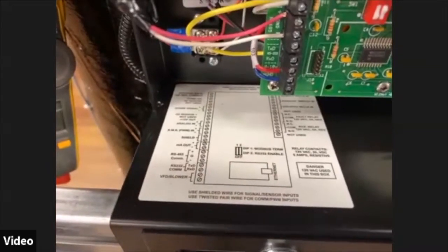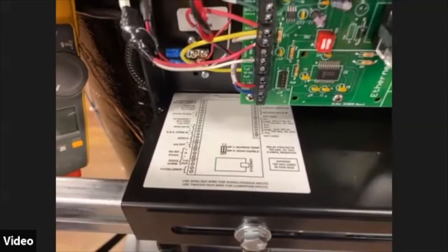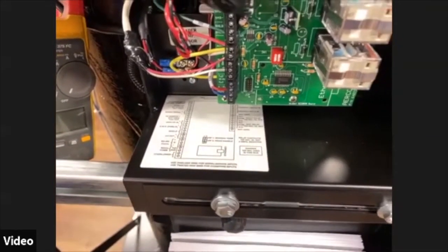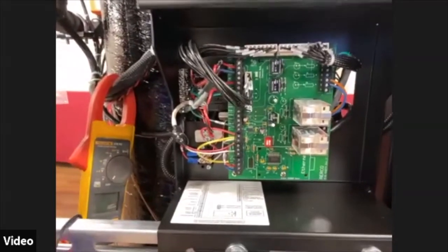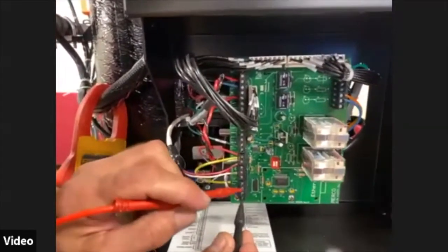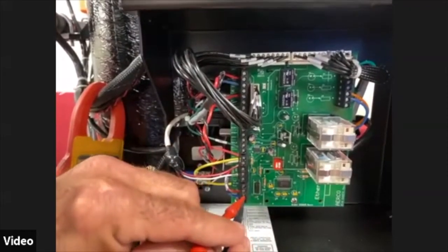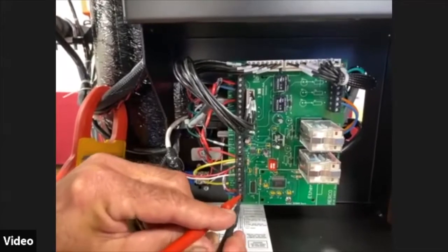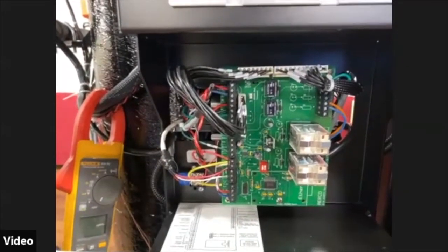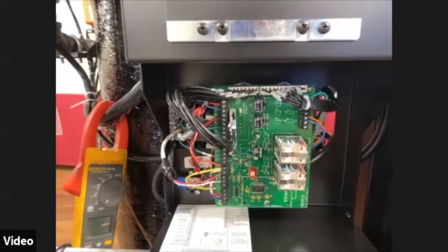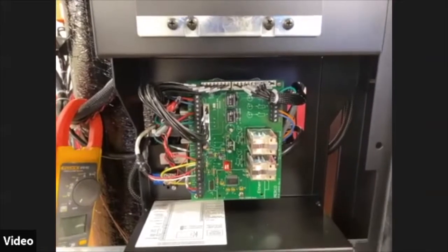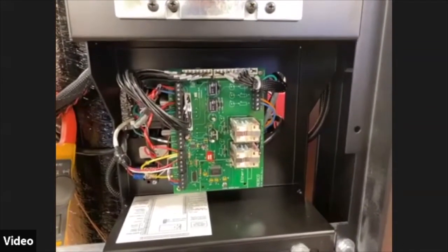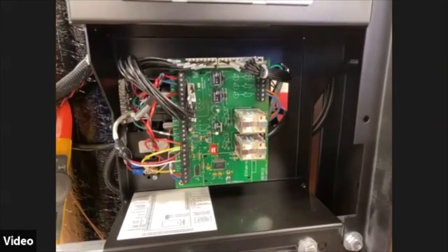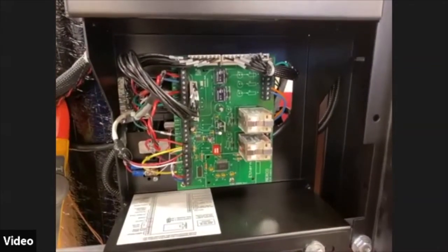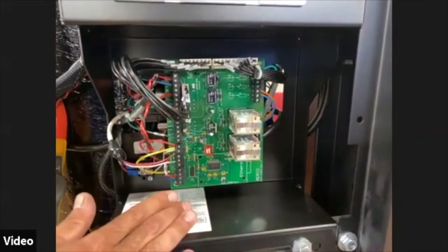But right here is a red and blue wire at the bottom. These wires are for checking your output voltage to the blower. So if you know what speed the blower is running at, or what speed you think it should be running at, you can simply go ahead and put a meter across the two of these and take a DC voltage reading on your meter, and it will give you that voltage output. It should match the voltage output that the boiler is specifying. If not, something's wrong. So you may have to start digging a little bit deeper into what's actually causing that problem. Could just be a bad blower motor, could be a number of different things. So that's how you'll check that.